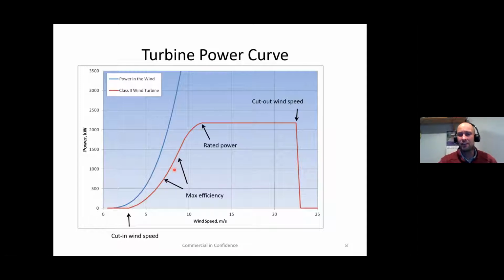In this part of the power curve, turbines are most efficient. Turbines convert about 40 to 45% of the energy of the incoming wind into electricity, and that's in this part of the power curve. Designers aim for the turbines to be most efficient at the most common wind speeds, around 6 to 9 meters a second, where the wind spends a lot of time at windy locations. At these speeds, the ratio of the red curve to the blue curve is about 45% - that's the peak efficiency of the turbine.